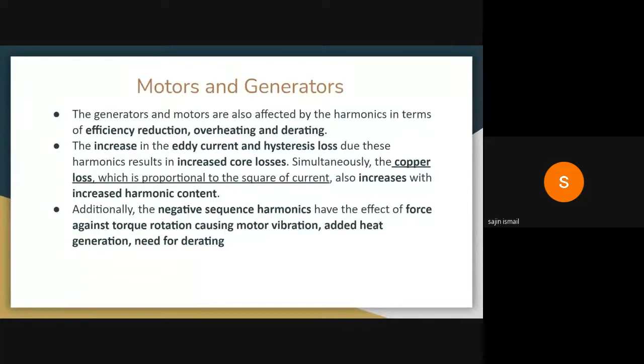And the negative sequence harmonics also affect the force against torque rotation, causing motor vibration, added heat generation, and the need for derating. So this is the effect on generators and transformers. Harmonics will create issues, whoever is the cause of it, whether the electric vehicle charging infrastructure, that means chargers or inverters or whatever it is. It will create issues for all the equipment associated with the grid or with the system. So reduction of harmonics is a very important aspect for any grid operator. So the loads are changing to nonlinear, and with the impact of electric vehicles, the change will be very high. It will be rapid, and the volume of it will also be substantially high.